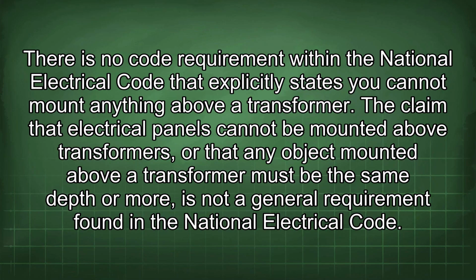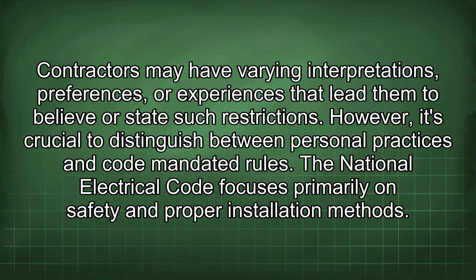There is no code requirement within the National Electrical Code that explicitly states you cannot mount anything above a transformer. The claim that electrical panels cannot be mounted above transformers, or that any object mounted above a transformer must be the same depth or more, is not a general requirement found in the National Electrical Code. Contractors may have varying interpretations, preferences, or experiences that lead them to believe or state such restrictions. However, it's crucial to distinguish between personal practices and code-mandated rules.